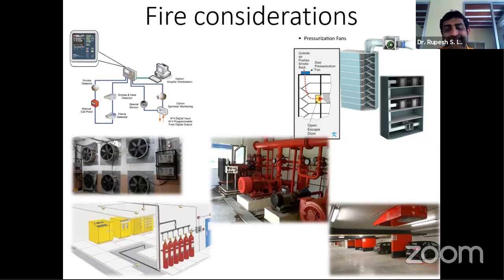But when these fans are coupled with a sensor, it's not like the fans are always on, or the fans are always off, because the fire requirement may need us to have the fans installed, but many buildings may not have these fans on. The reason being it may consume too much energy. But from a safety point of view, I think these need to be kept on. And if energy is the issue, then putting a variable speed drive, trying to get the fans to operate at a level or at a location only where the pollutant is present. For example, in a basement, if one side of the basement is having parking and is having carbon monoxide, those fans can run at that optimum speed. And the rest of the basement, which probably may not have any occupancy of vehicles, could run at that minimum air changes per hour in order to keep some air circulation and from a safety point of view. So those can be incorporated and power could be reduced.